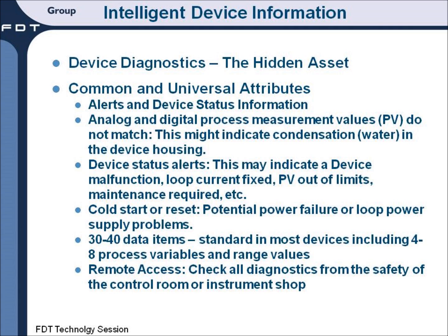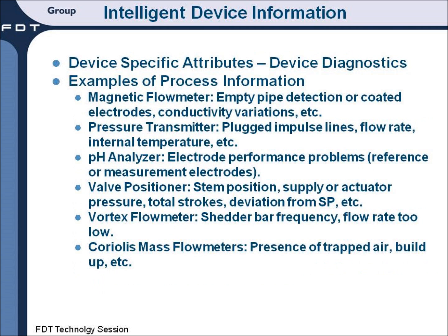These data items are actually available by remote access. So checking all the diagnostics from the safety of a control room or an instrument shop is now as simple as clipping on to the 4 to 20 milliamp signal or the digital communication bus to be able to determine what the potential problem was that caused the alert.